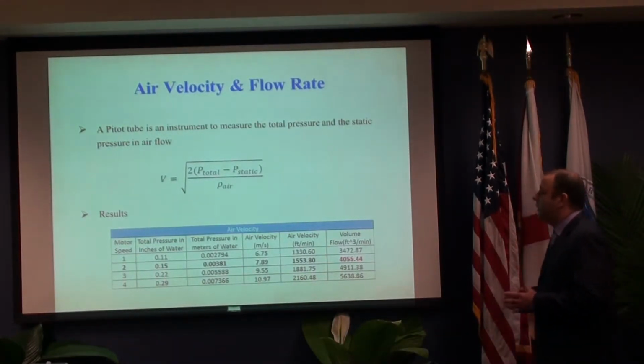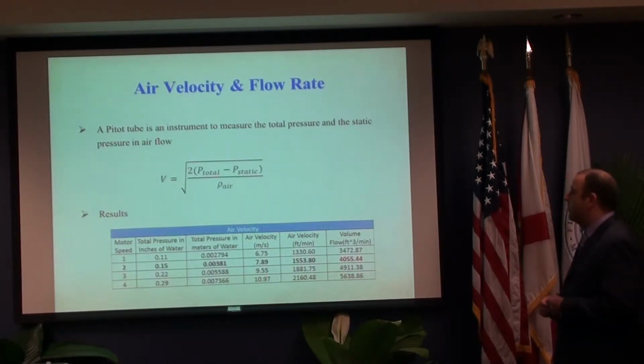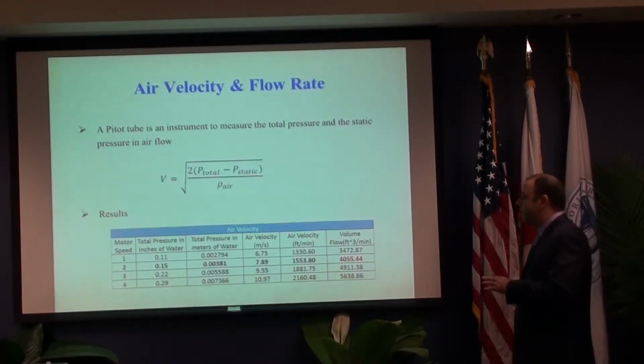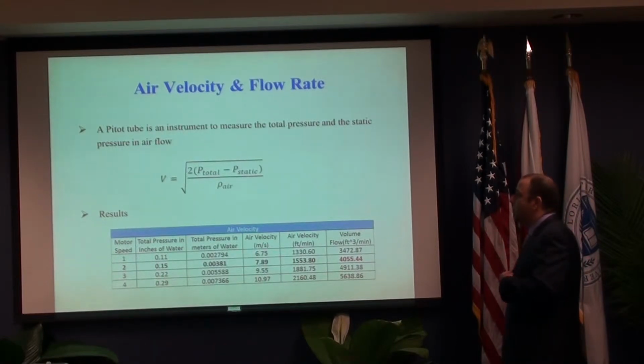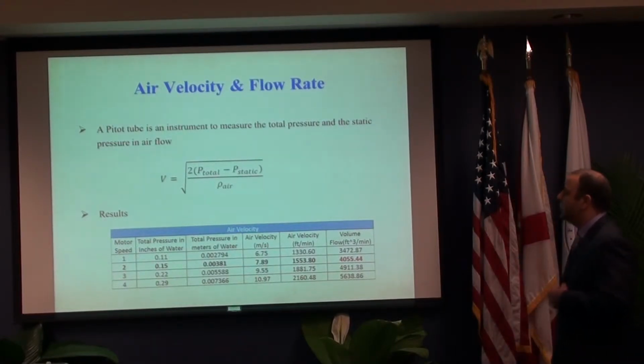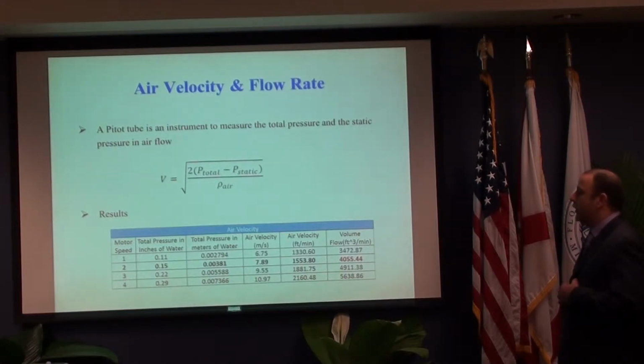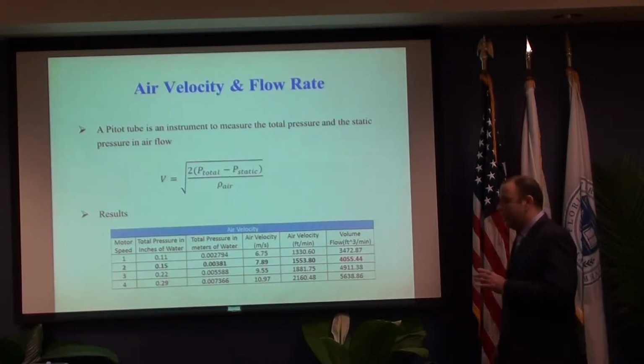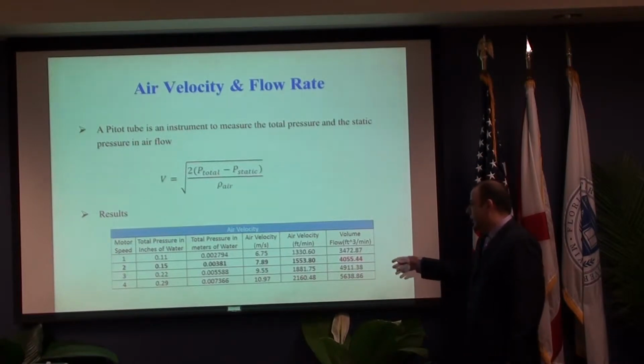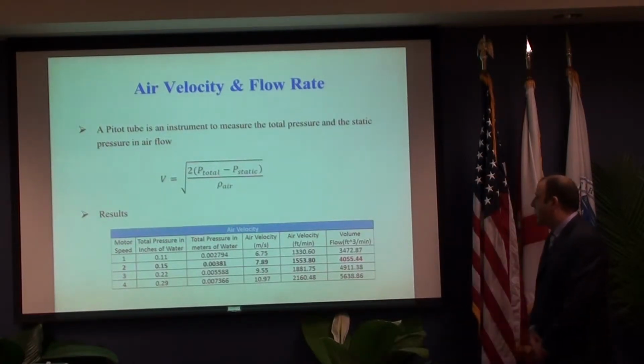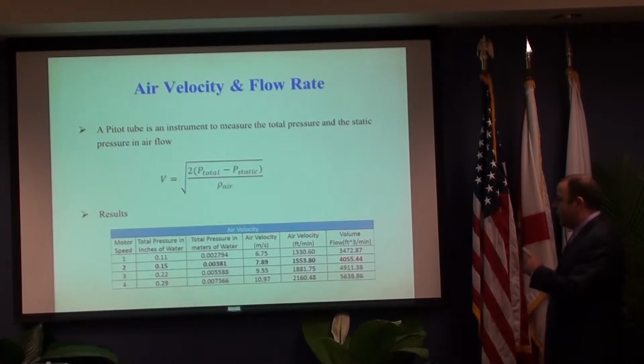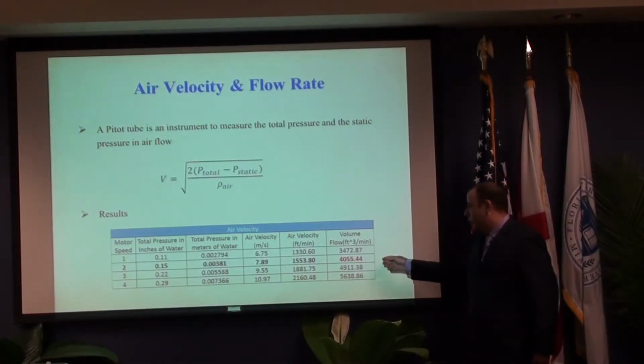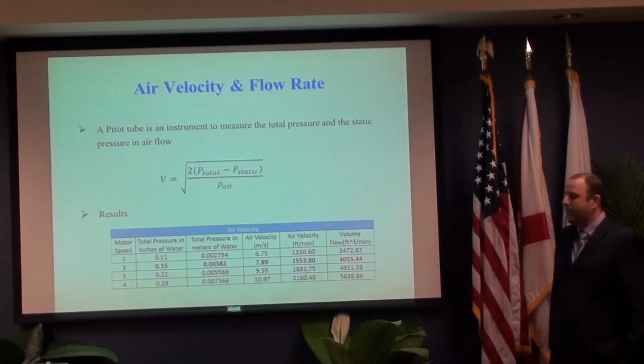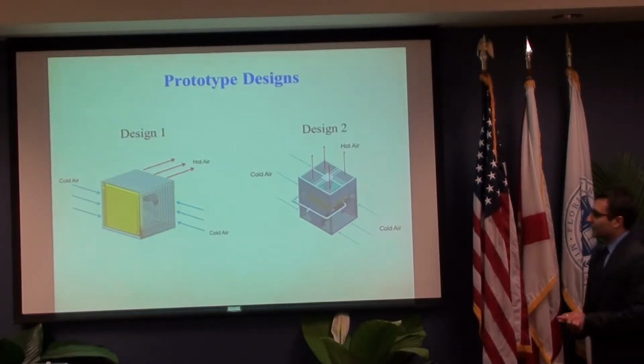Next, we calculated the velocity in order to find the volumetric flow rate. We calculated the velocity using the pitot tube. The pitot tube is an instrument to measure the total pressure and the static pressure in a flow. For the results of the 4 different speeds, the first speed has 3472.87, the second one 4,055, the third one 4,911, and the last one. So we chose to have 4,055 cubic feet per minute. On our design, we have 2 designs.